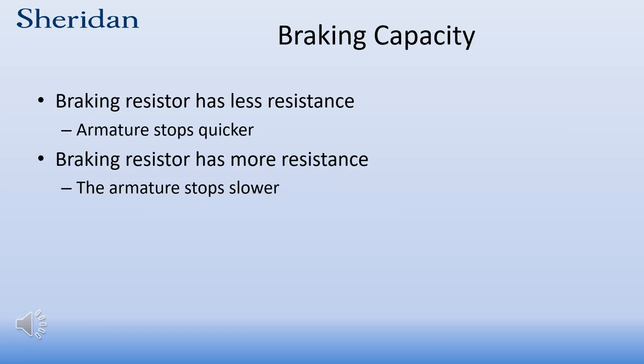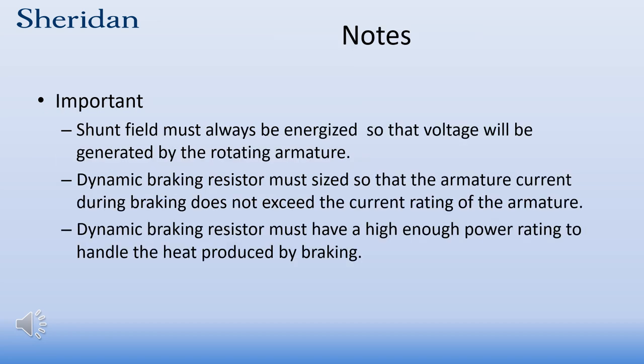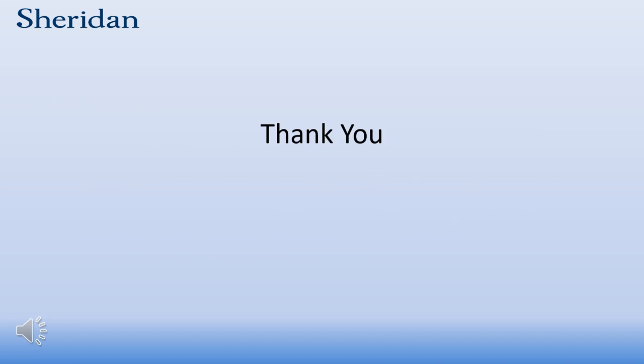When it comes to braking capacity, the value of resistance is important. If the resistor has less resistance, more current will flow and the motor will stop quicker. If it has greater resistance, there will be less current and the motor will take longer to stop. Important notes: the shunt field must always be energized during braking to produce an armature voltage; the resistor must have a high enough resistance value so that too much current does not flow through the armature; and the resistor must have a high enough power rating to handle the heat produced by braking. Thank you for watching this Sheridan College presentation on dynamic braking.